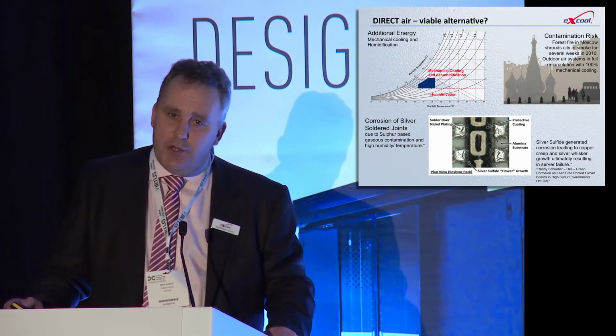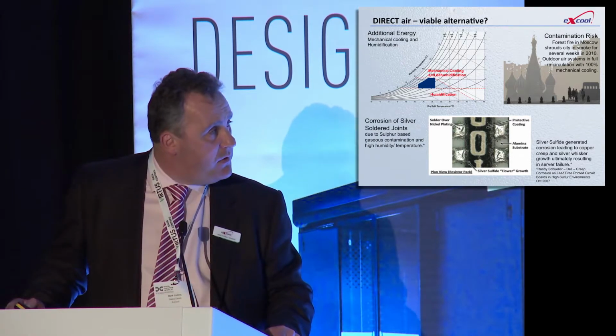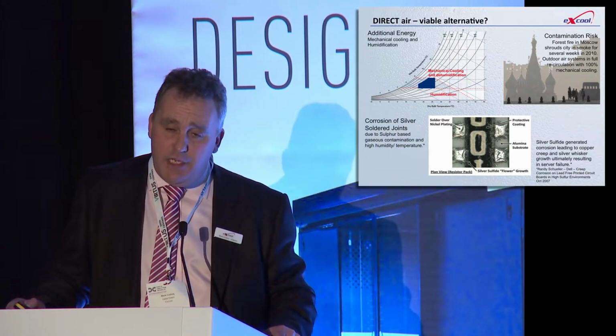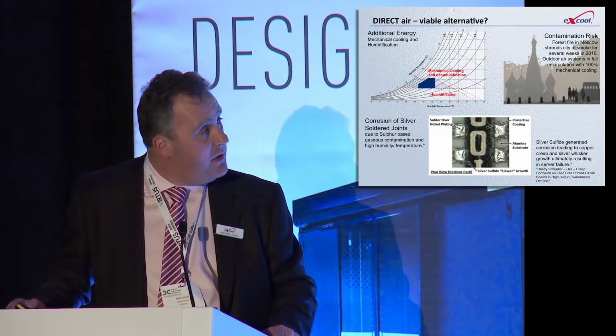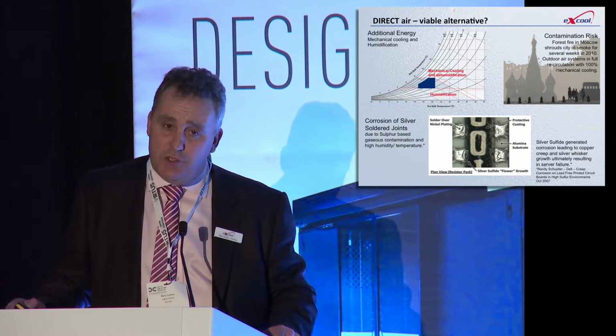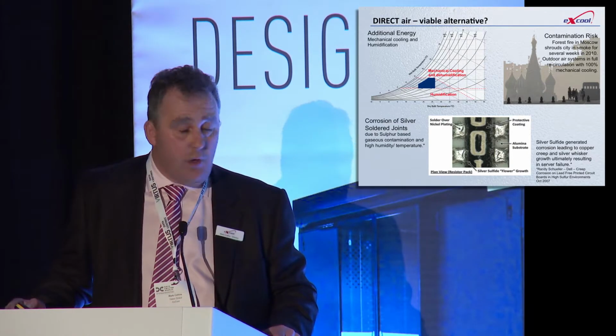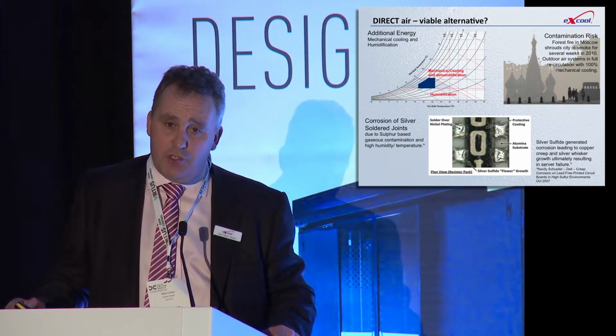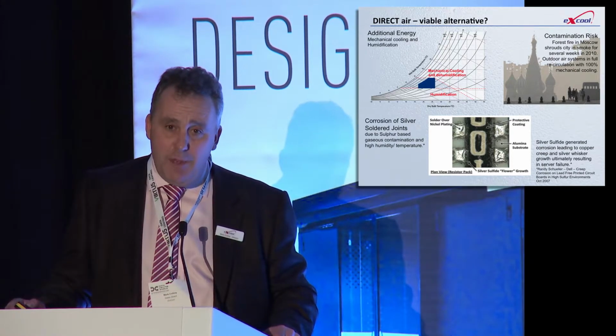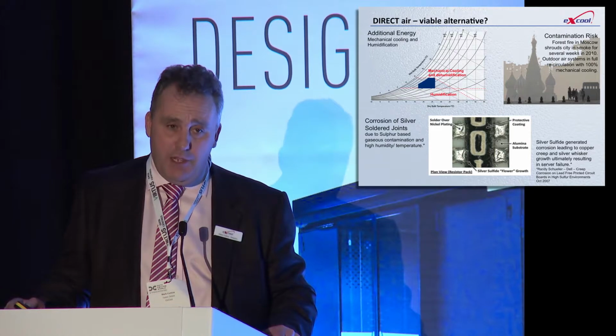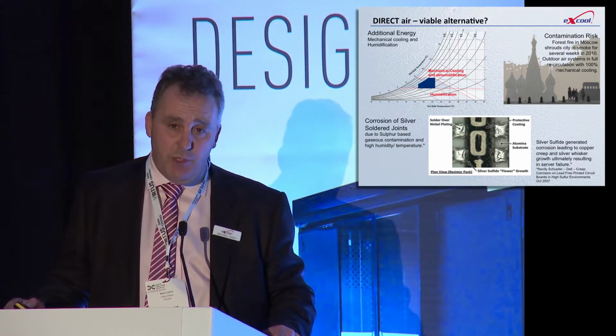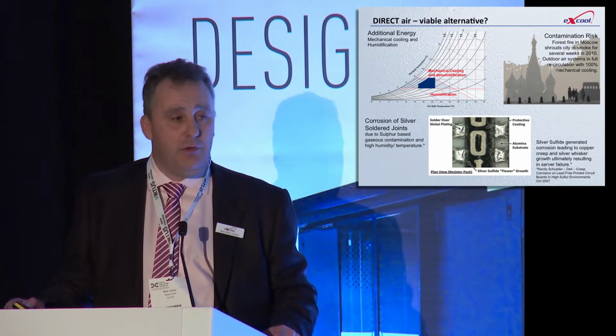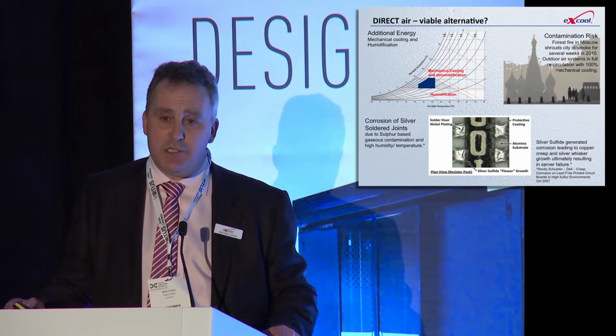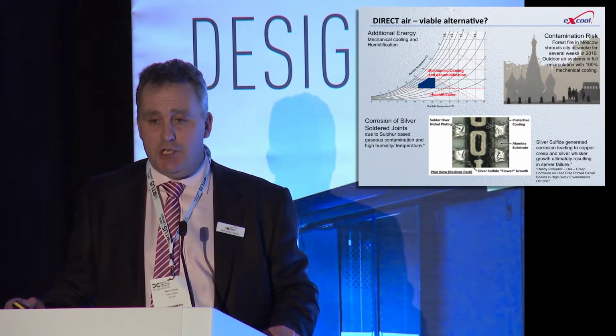This is where it gets quite interesting as well. We've got a psychrometric chart here. The blue zone is the envelope recommended by ASHRAE. To maintain those conditions, if the outdoor air condition is within the zone that's just gone up on the screen there, you'll need mechanical cooling and dehumidification. Some choose to ignore that and allow humidity to rise in the space, which can result in condensation on the racks.